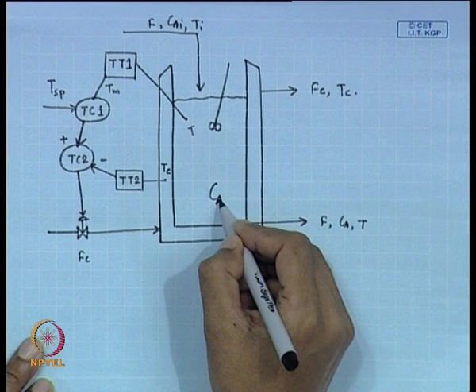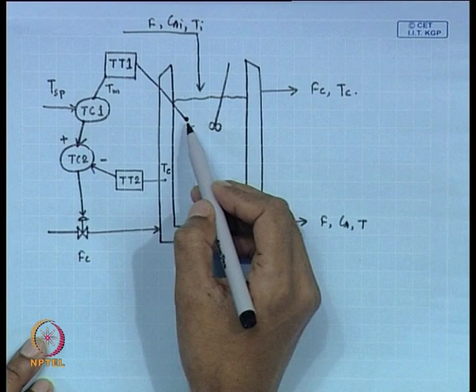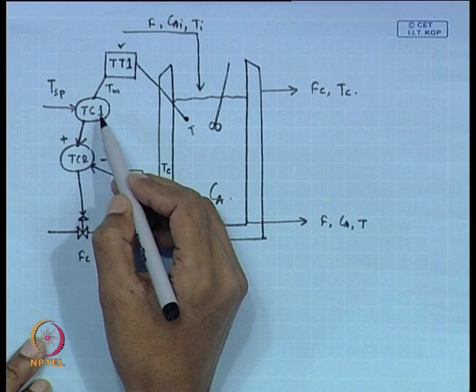Fine. So, I am repeating the steps again. Our control objective is to maintain the temperature T. So, this reactor temperature is measured by the measuring device TT1. Then the measured temperature Tm is compared with its set point value. Then TC1 calculates the control action. For the simple feedback controller, the control action of TC1 is implemented, but here another controller is included, that is TC2. Here the first temperature controller TC1 calculates basically the set point value of coolant temperature.